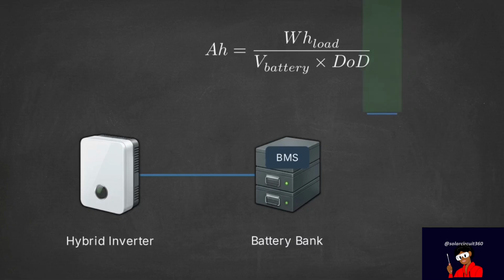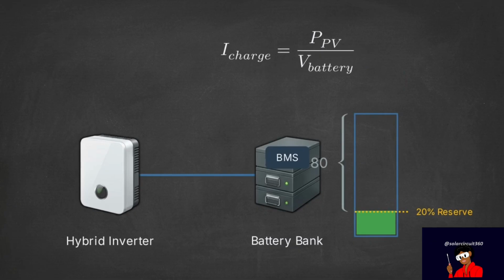The storage component connects the inverter to a battery bank and its battery management system, or BMS, which monitors and protects the cells. To calculate required capacity in amp hours, divide the load's watt hours by the battery voltage times the depth of discharge. Depth of discharge is the percentage of the battery drained relative to overall capacity. Restricting this preserves cell longevity. Pushing power back into the battery has strict limits. Maximum charge current equals total PV power divided by battery voltage. The inverter's output must be throttled below the battery's maximum charge current.